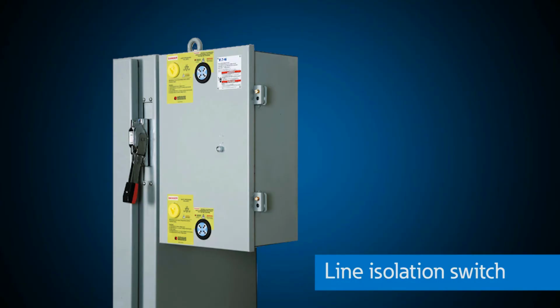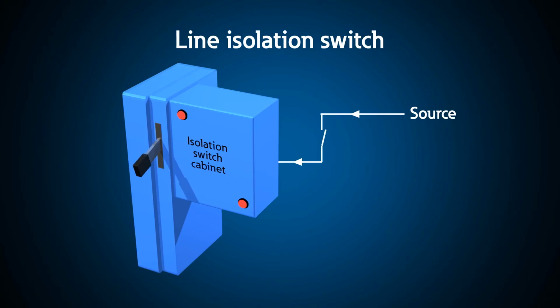Line isolation switches create an external connection point for enclosed control cabinets, allowing you to lock out a switch and completely isolate the inside of the control cabinet, like a VFD. In most applications, the incoming breaker or connection point inside one of these control cabinets has line voltage and again must be considered as live for arc flash considerations.